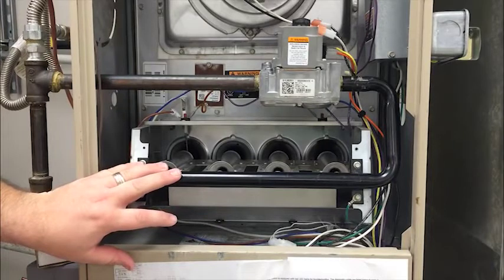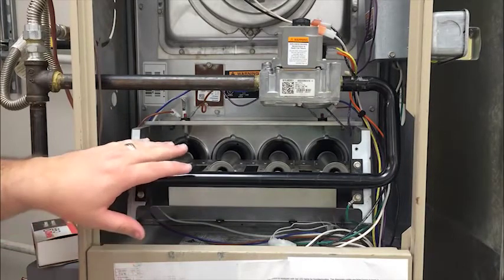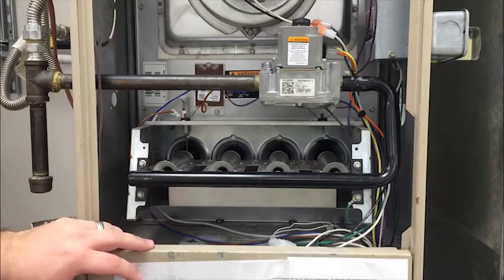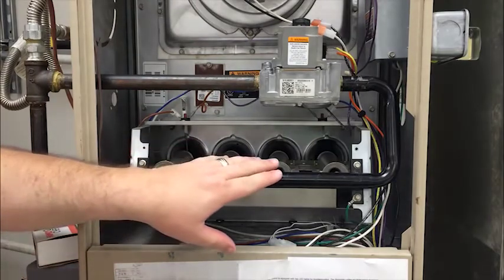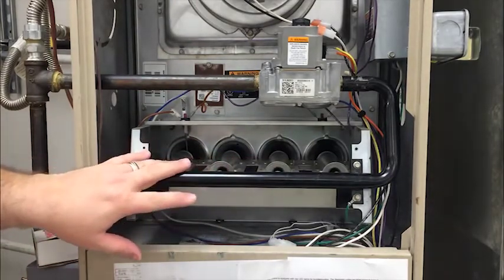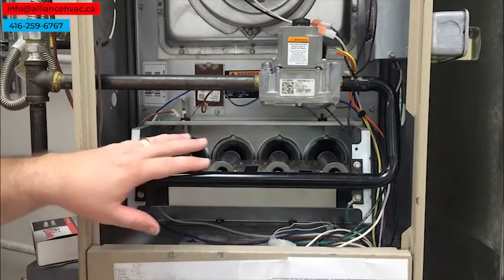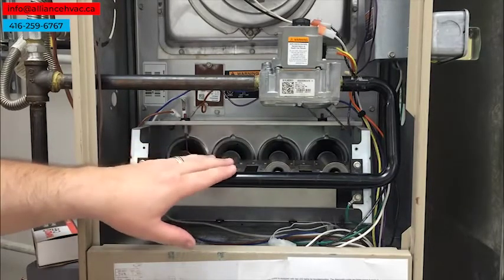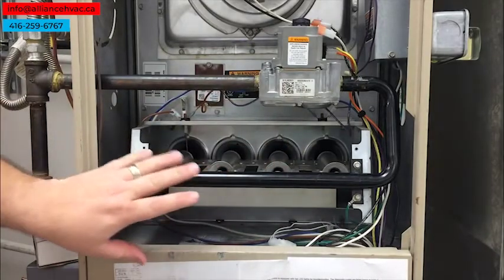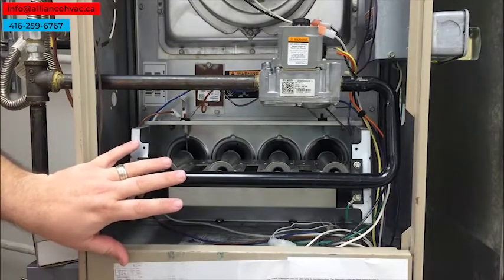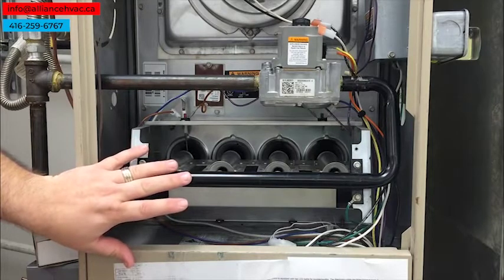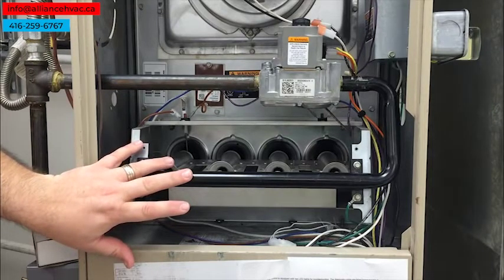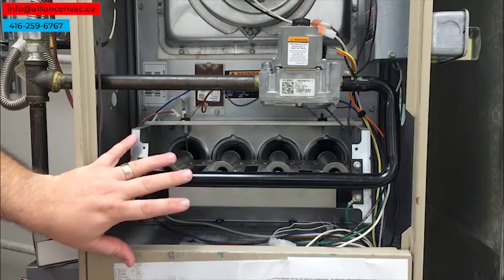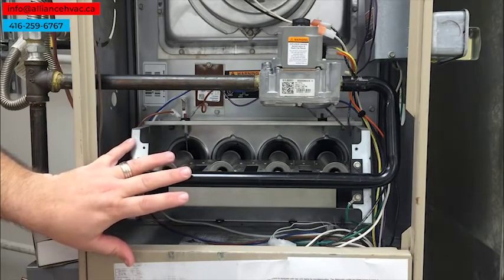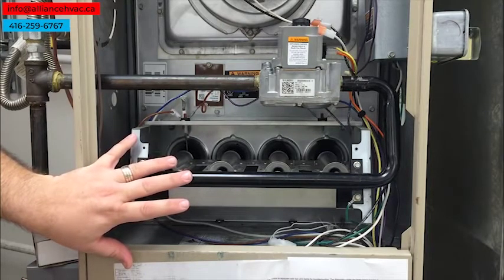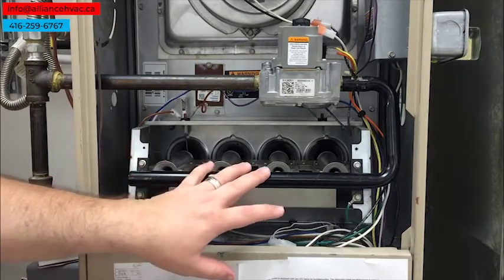I want to talk to you today about testing a furnace heat exchanger that you think might be cracked or damaged. This can be a tricky situation for some people to inspect. Some really don't know the simplest and easiest ways to test them. While it's true we can disassemble the heat exchanger, take the manifold and burners out, and do a visual inspection, and then come in with inspection cameras or multiple mirrors and flashlights, there's a very simple test you can perform first, typically without having to disassemble anything: the static pressure test.